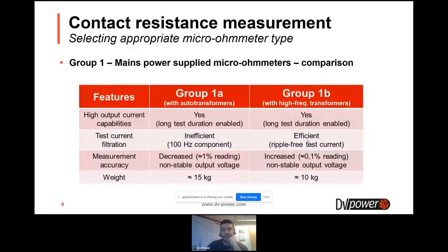Basically, these are differences, as I said, but usually the weight of this group 1B with high frequency transformers is less than 10 kilos, and the weight of this first group with the auto transformers is more than 50 kilos.